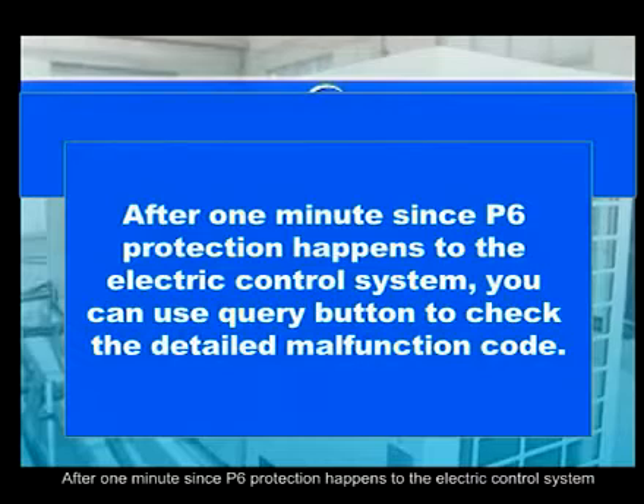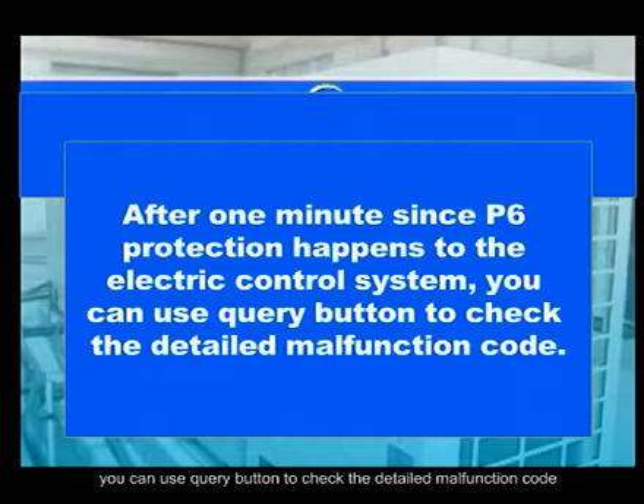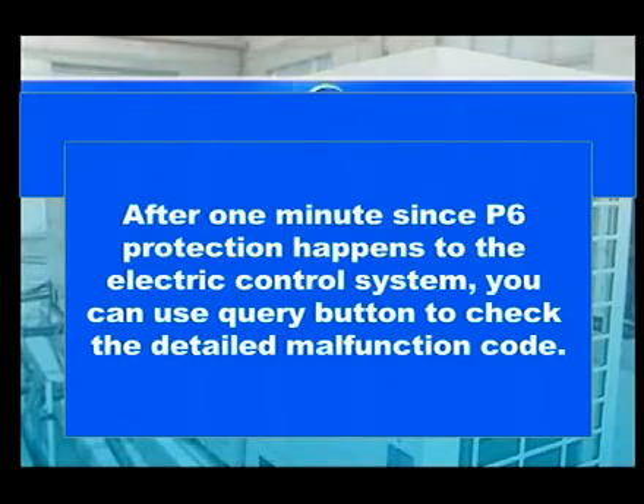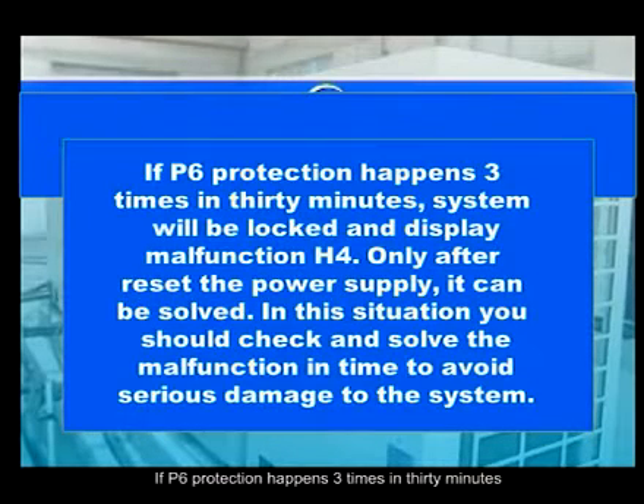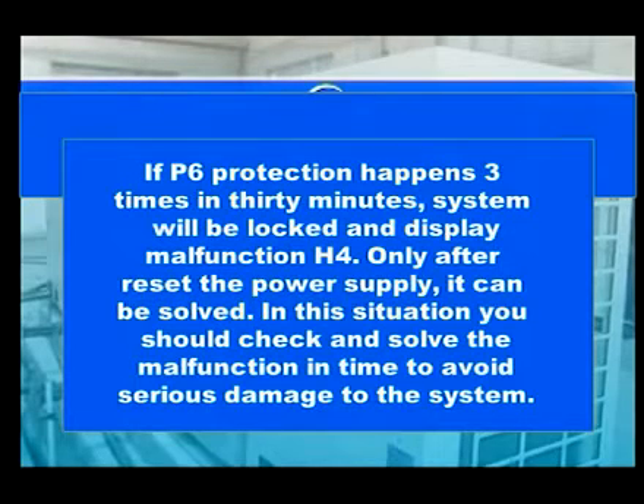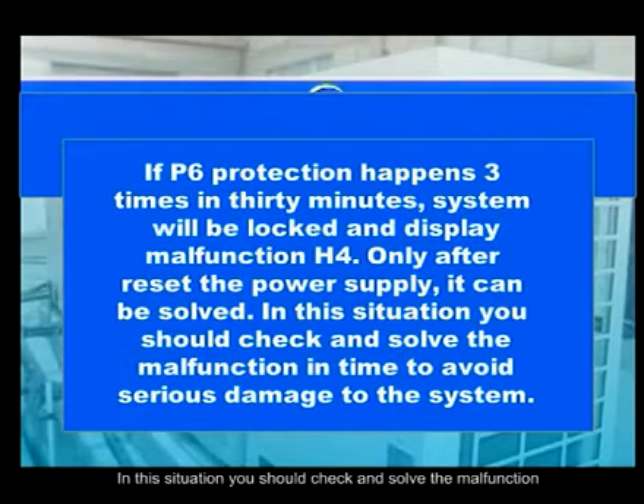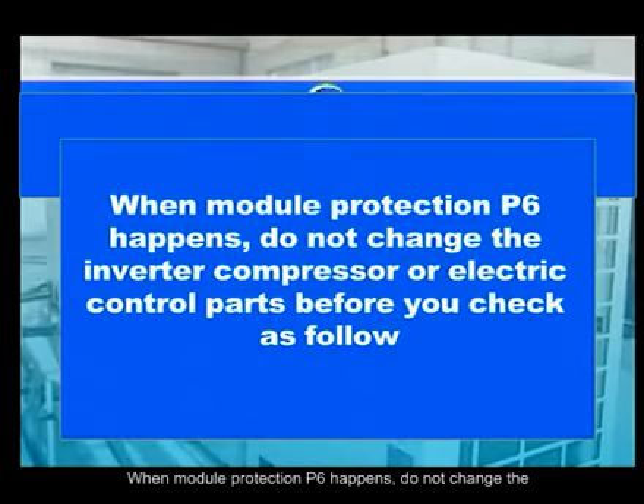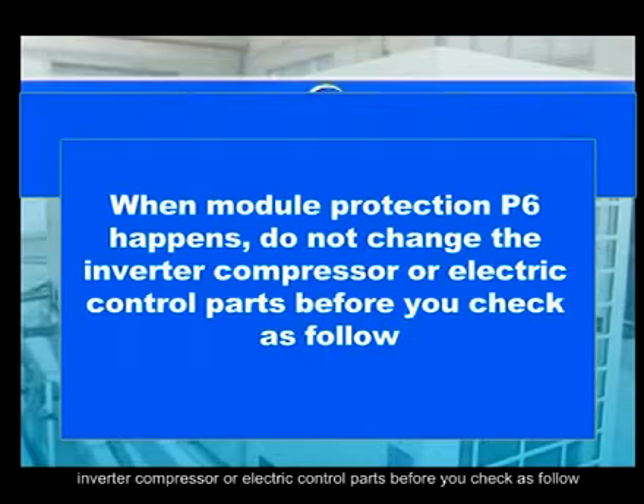After 1 minute, since P6 protection happens to the electronic control system, you can use the Query button to check the detailed malfunction code. If P6 protection happens 3 times in 30 minutes, the system will be locked and display malfunction H4. Only after resetting the power supply can it be solved. In this situation, you should check and solve the malfunction in time to avoid serious damage to the system. When module protection P6 happens, do not change the inverter compressor or electric control parts before you check as follows.